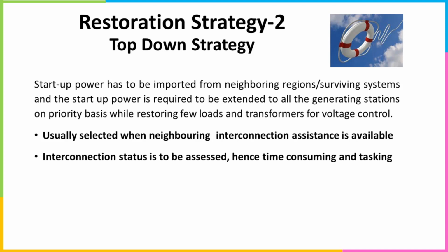On the other side is the bottom-up approach. You start from the smaller power plants, you bring those power plants back into the system, and then you start restoring the load. That is, you are entirely dependent on your own generation or your own capability. Second is the top-down approach. When you have a neighboring system which is surviving, then they can extend power to you so that you can restore, because those will be a very large island, or an area having a significant amount of inertia. So those are very stable kinds of scenarios. So they can supply the power to you. The only issue is the cranking path, whether the cranking path has adequate reactive support available.